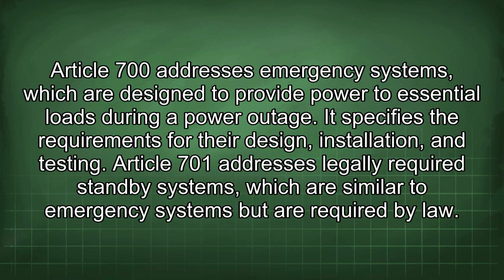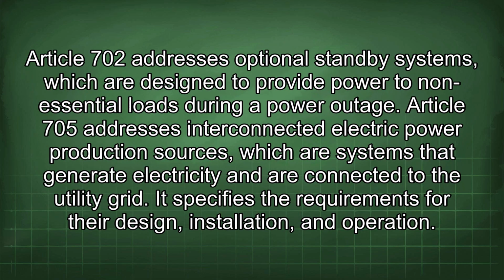Article 700 addresses emergency systems, which are designed to provide power to essential loads during a power outage. It specifies the requirements for their design, installation, and testing. Article 701 addresses legally required standby systems, which are similar to emergency systems but are required by law. Article 702 addresses optional standby systems, which are designed to provide power to non-essential loads during a power outage. Article 705 addresses interconnected electric power production sources, which are systems that generate electricity and are connected to the utility grid. It specifies the requirements for their design, installation, and operation.